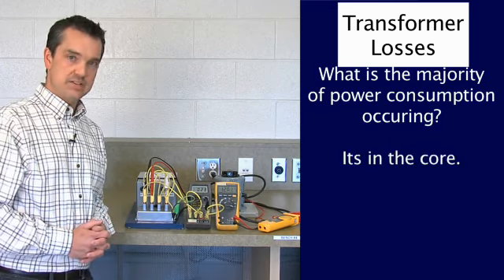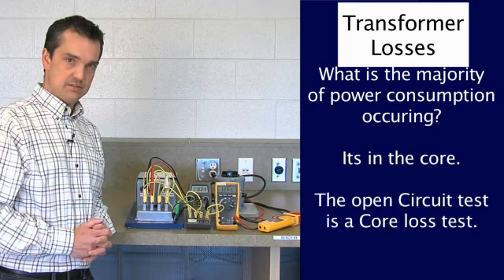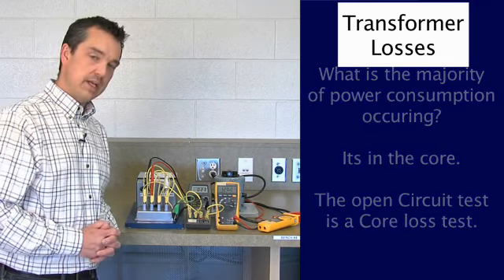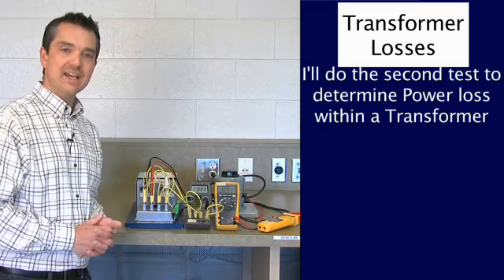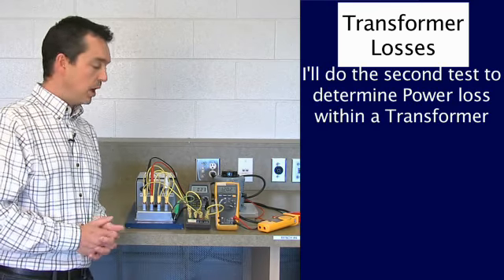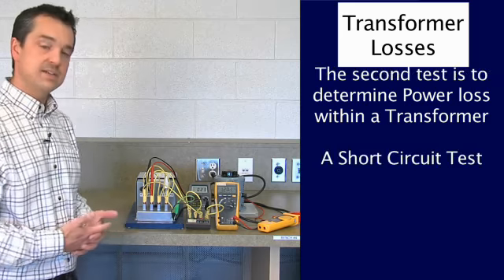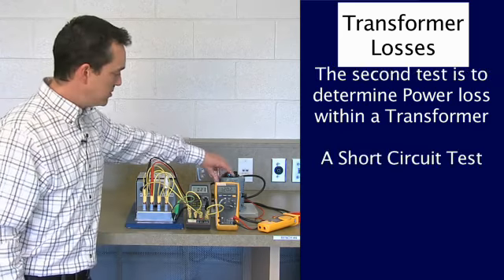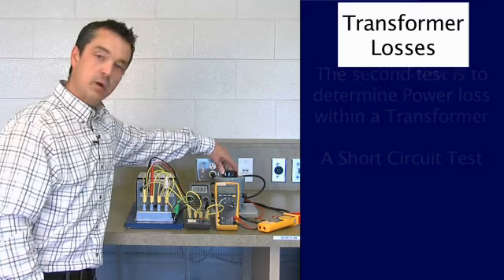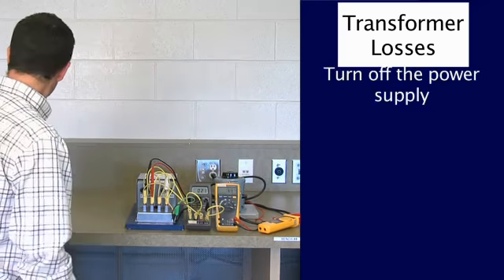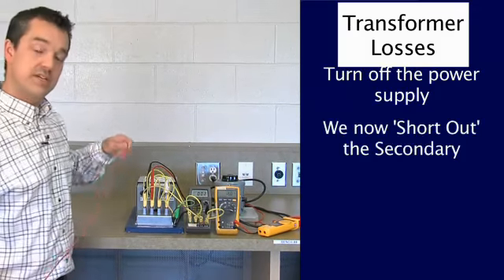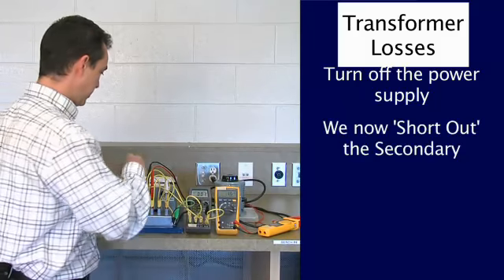So your open circuit test is a core loss test. While I have this all connected, I'm going to continue on with the second test to determine power loss within a transformer. That second test is a short circuit test. So all I'm going to do is turn off my power supply, and I'm going to, like the test would imply, short out my secondary.